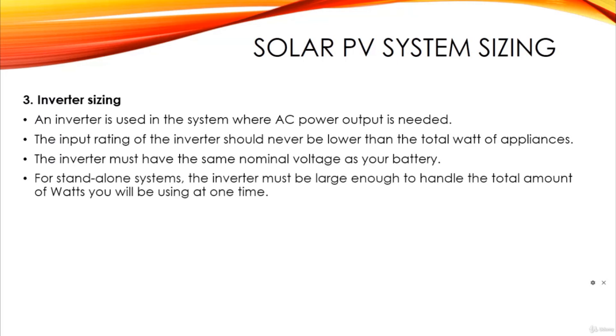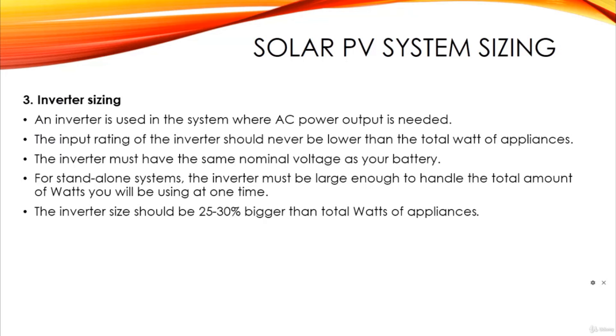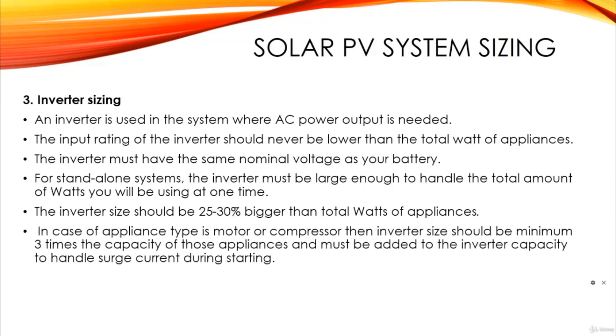The inverter must have the same nominal voltage as your battery. For a standalone system, the inverter must be large enough to handle the total amount of watts you will be using at one time. The inverter size should be 25 to 30 percent bigger than the total watts of the appliances. In the case of motor or compressor appliances, the inverter size should be a minimum of three times the capacity of those appliances.